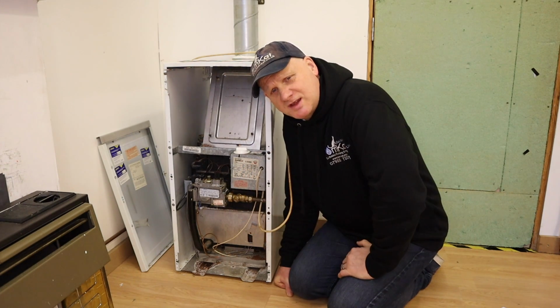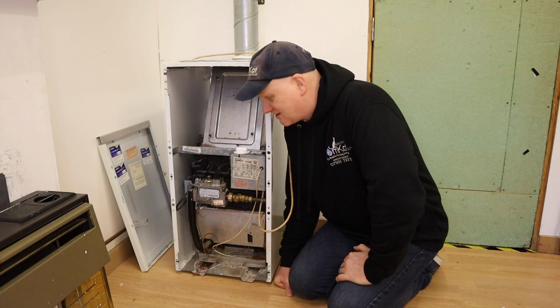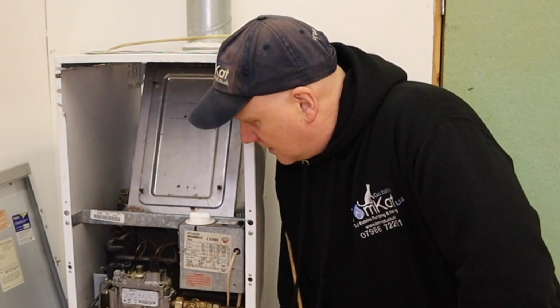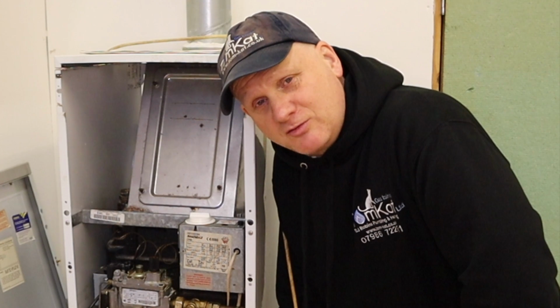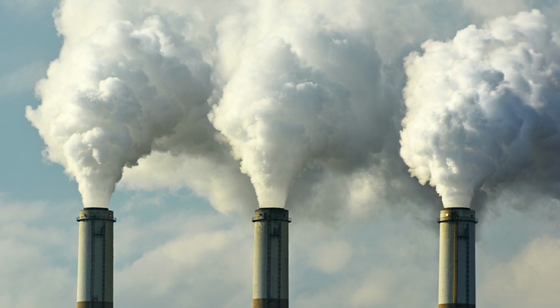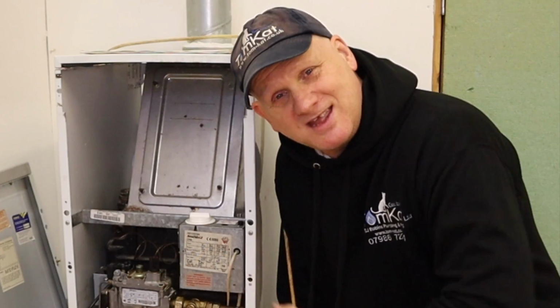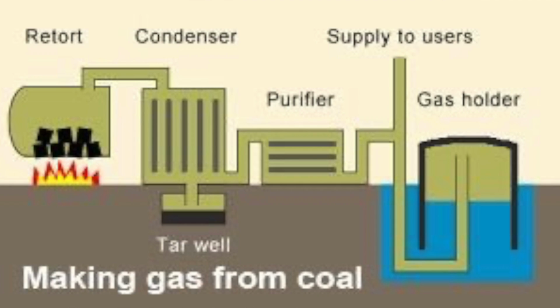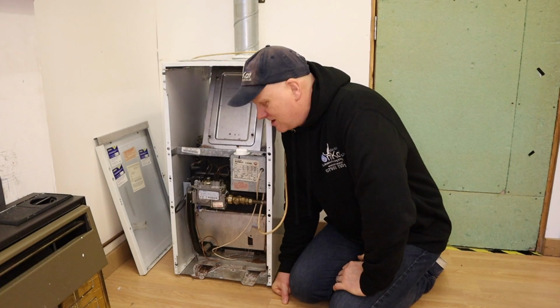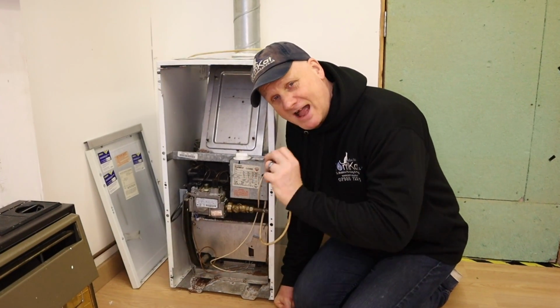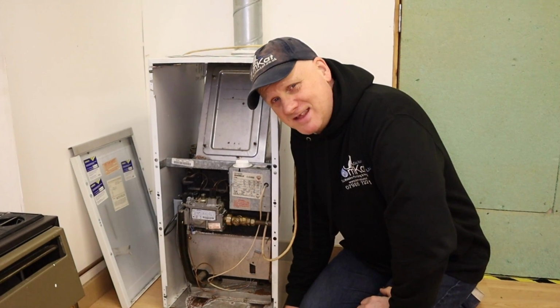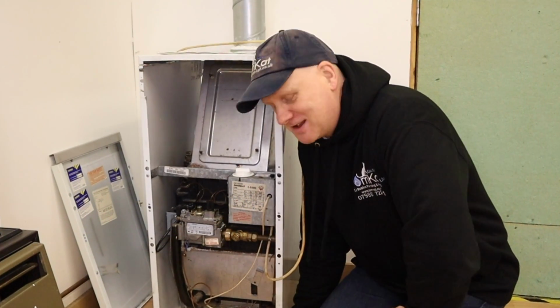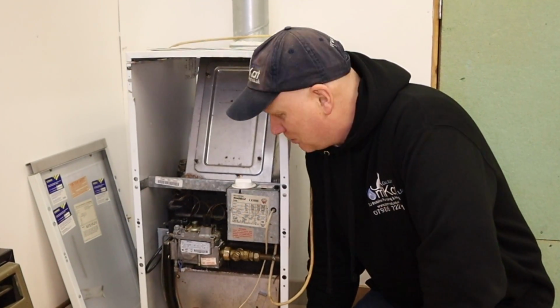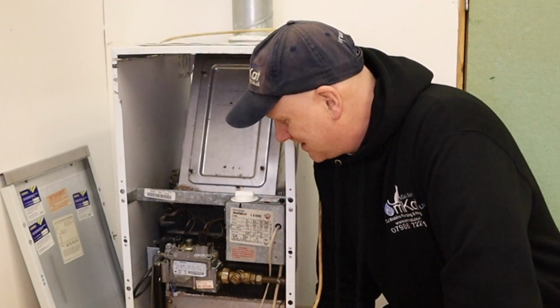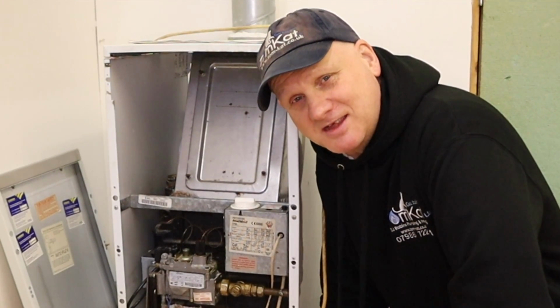Now, originally we used cast iron heat exchangers because of how robust it is. It doesn't break very easily. And they also originally used it because it had tolerance to sulfurous flue gases, which is a byproduct of burning coal. So when these things first came out, we weren't on natural gas, we were on coal gas, or Towns gas. And the reason why some of these are still around today is because of how robust they are, and because they have large waterways, so they don't block up very easily. But if you do have one of these and it sings like a kettle, then it is getting blocked up with limescale. And like I say, we shouldn't be having these in today's society.